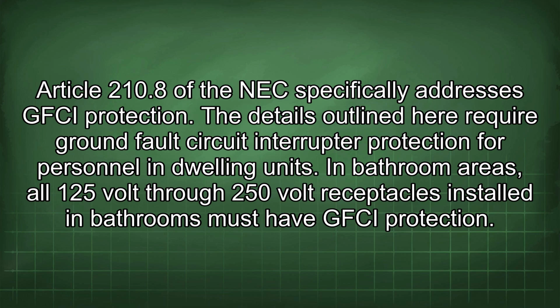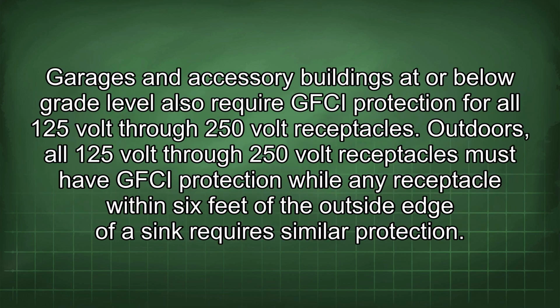The details outlined here require ground fault circuit interrupter protection for personnel in dwelling units. In bathroom areas, all 125 volt through 250 volt receptacles installed in bathrooms must have GFCI protection. Garages and accessory buildings at or below grade level also require GFCI protection for all 125 volt through 250 volt receptacles. Outdoors, all 125 volt through 250 volt receptacles must have GFCI protection, while any receptacle within 6 feet of the outside edge of a sink requires similar protection.